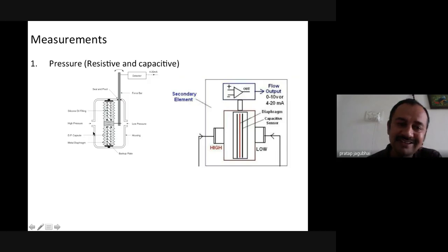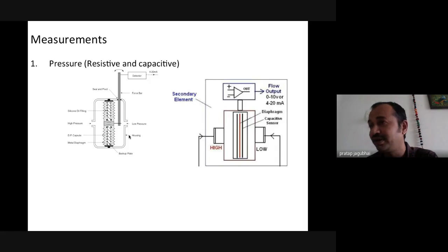So here you measure a static pressure if you block one side. So you can measure static pressure with the help of resistance change, and you can measure differential pressure also with the help of this deflection. So in both ways, this resistance change can be detected by a Wheatstone bridge, which you know very well. And the voltage difference of this Wheatstone bridge is sensed with the instrumentation amplifier, and then it is given to the microprocessor based devices for the display.